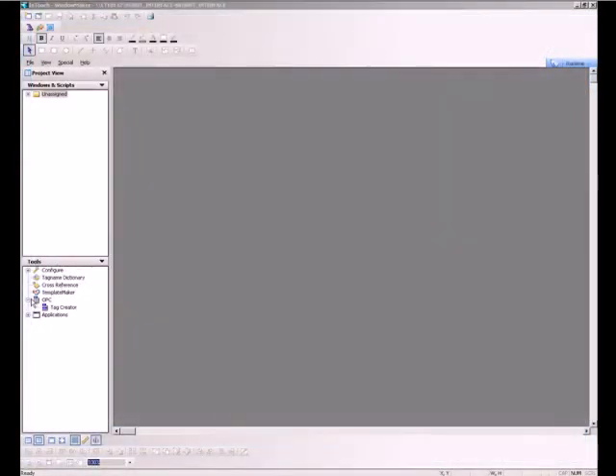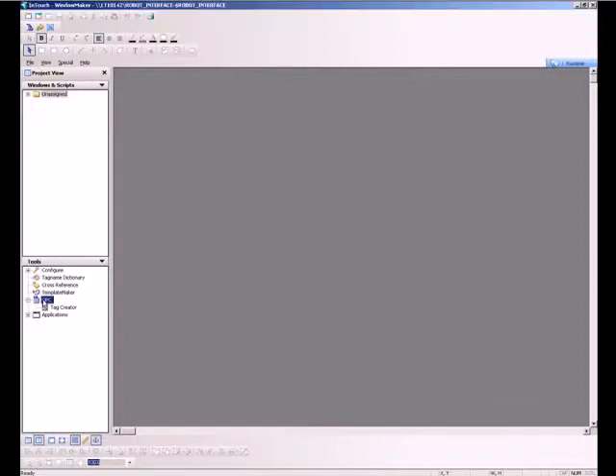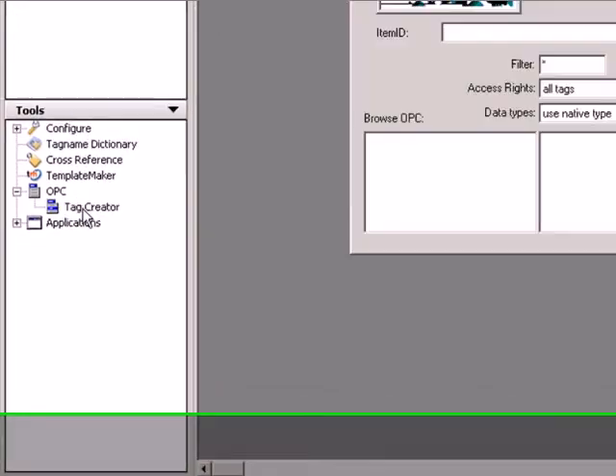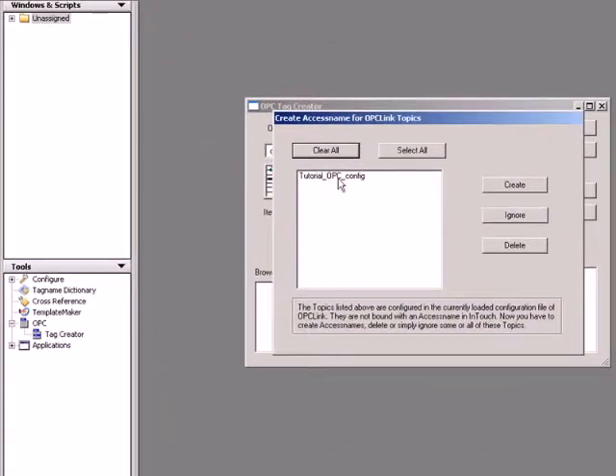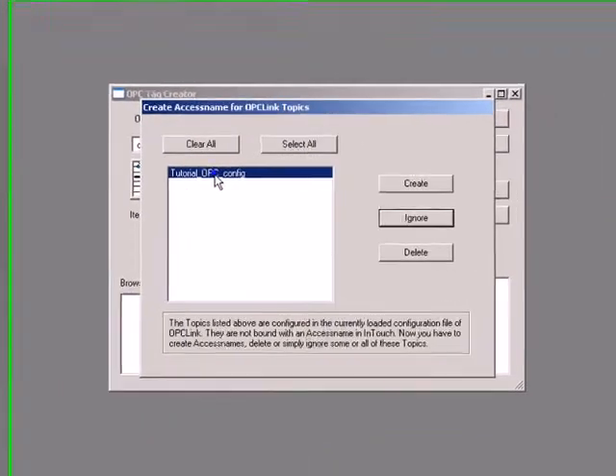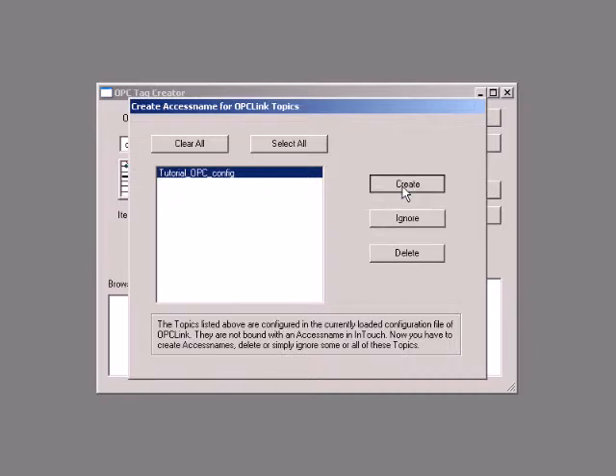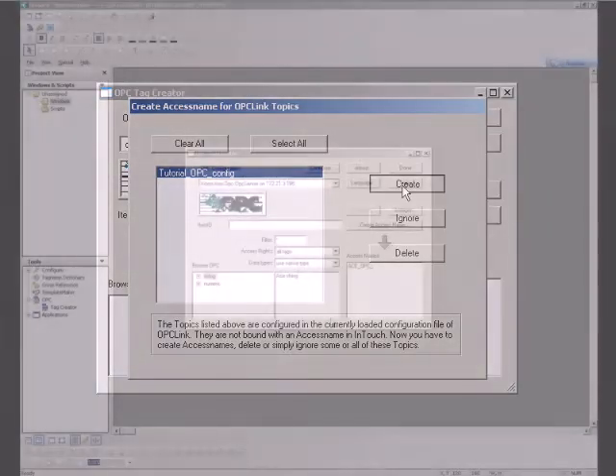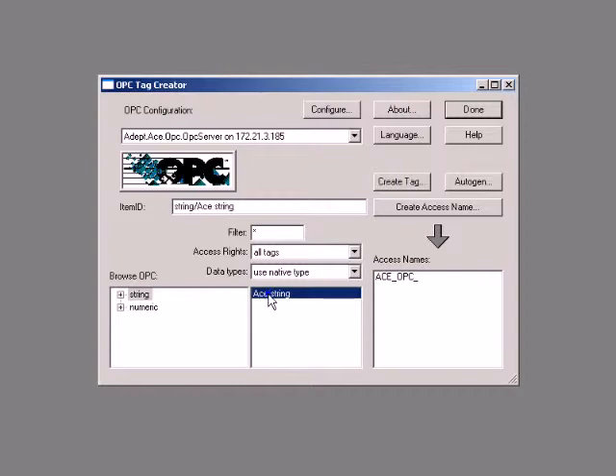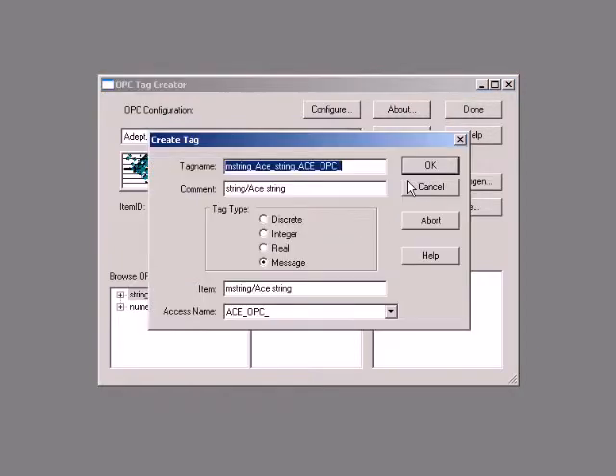We are going to use the OPC Tag Creator option, which is available under OPC in the Tools section. Double-click Tag Creator and select Tutorial underscore OPC underscore Config from the Topics list. To create an access name for the topic, click Create. From the Browse OPC list, click String and then select ACE String. Click Create Tag and then click OK.